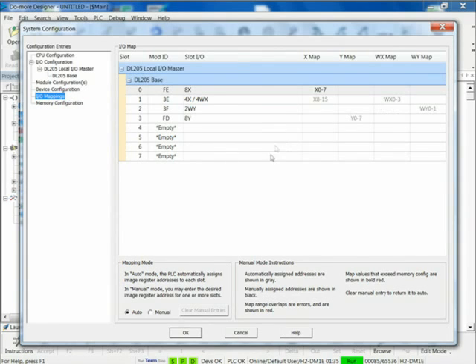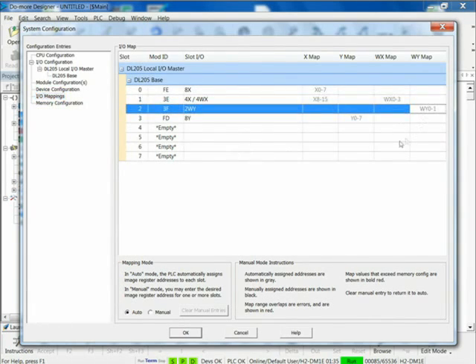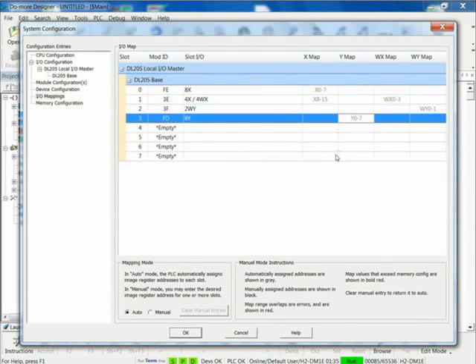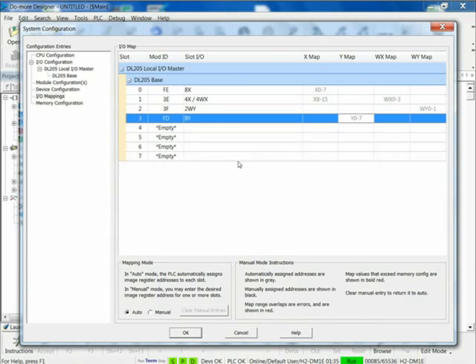We've got the two-channel output card which shows up as WYs, and we've got the eight digital outputs which show up as Y0 through 7. So that's the automatic mode, and if I want to, I can go down to manual and configure it. But that's where I do it. And again, all of this is under the umbrella of the System Configuration.